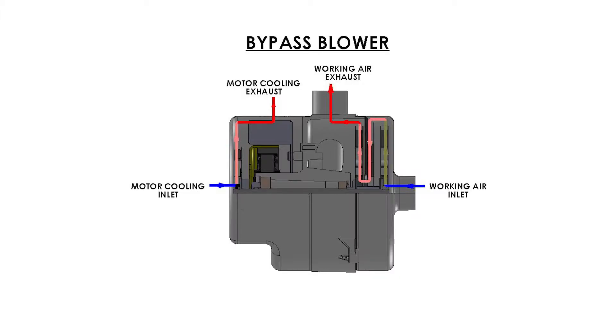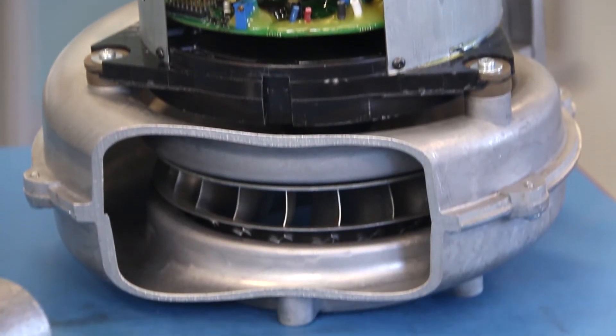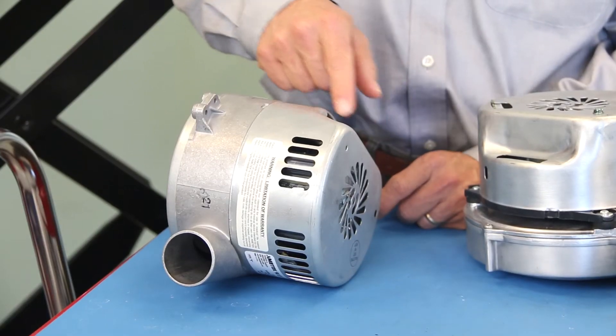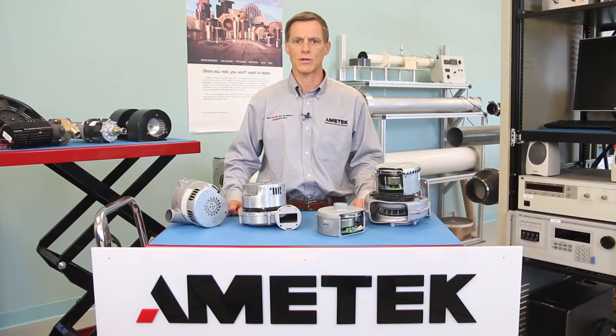A bypass design has two basic air movement sections to the blower: 1. The working air, meaning the functional purpose of the blower. 2. The motor and electronics compartment that requires clean, breathing-quality air circulation for proper thermal management of the blower. When designing the blower into an end application, it is critical not to recirculate the working air and cooling air, as that could result in overheating of the motor and electronics compartment.